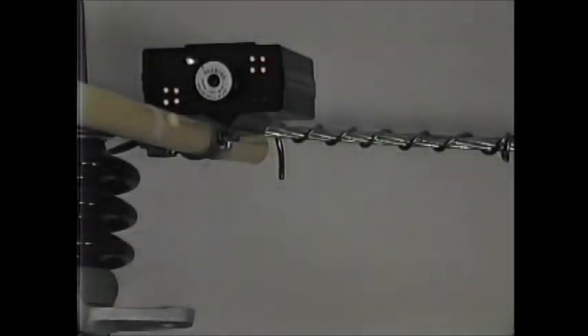Again, at the same voltage level, now instead of having the three lights we expect, we are picking up four banks of lights. The reason for this is the unit is installed very close to an insulator that has a grounded base.